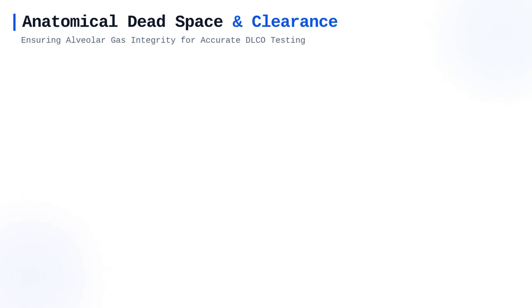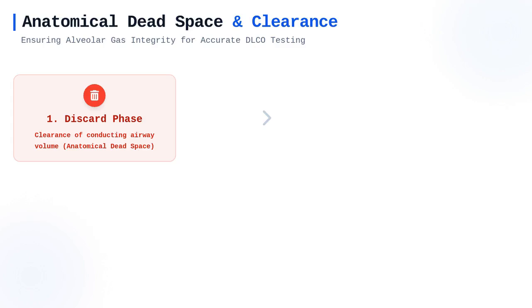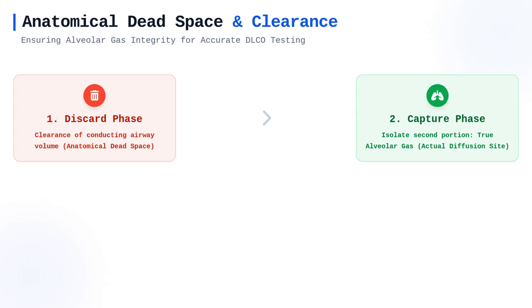The anatomical dead space must be cleared during the initiation of the exhalation phase so that the sample represents true alveolar gas. We accomplish this by utilizing a specific sample collection window, where the first portion of the exhaled gas, which reflects the volume of the conducting airways, is discarded. By isolating the second portion of the exhaled air, we capture gas that has been in contact with the alveolar surface where actual diffusion takes place.